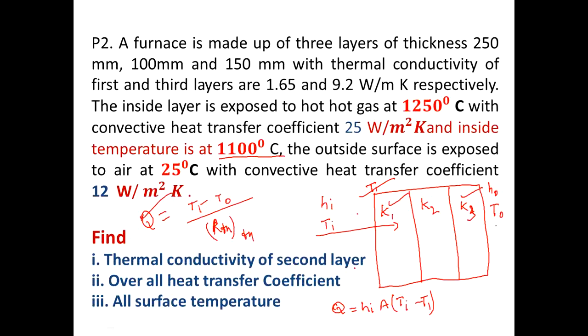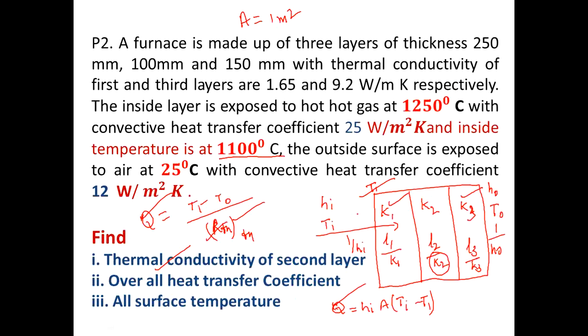In R thermal resistance, you know Q from this equation. R thermal resistance includes 1 by HI, plus L1 by K1, plus L2 by K2, plus L3 by K3, plus 1 by H0. Since A is not given, you consider A equal to 1 meter square. Therefore, you have all the thermal resistances, and the only unknown is K2. Then you can find the thermal conductivity K2 by equating this heat transfer. TI is 1250 degrees Celsius and T0 is 25 degrees Celsius, so you can find K2 easily.